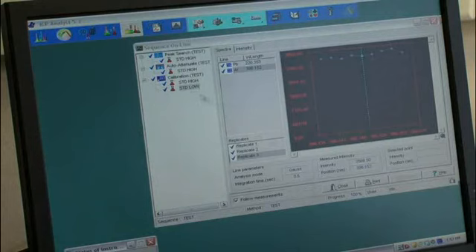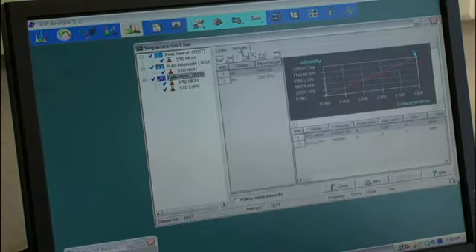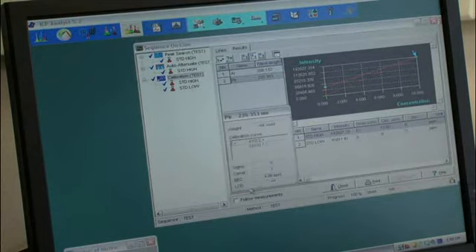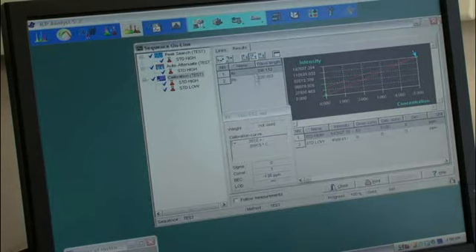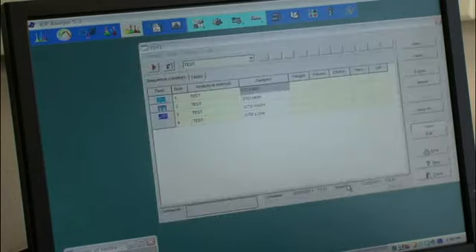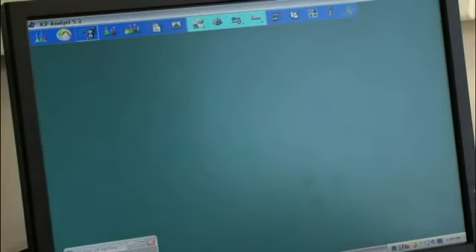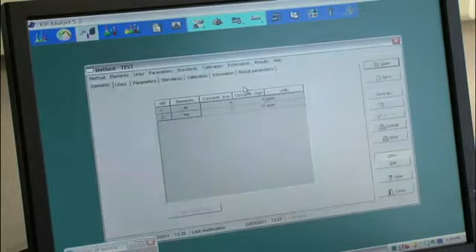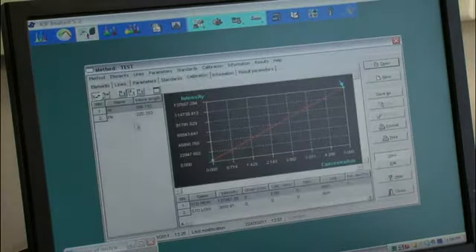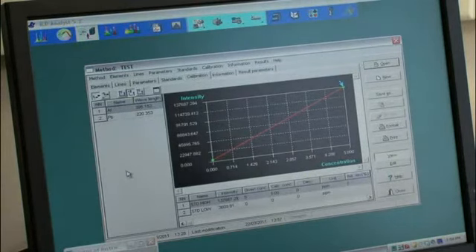Okay, so here we can click to see what our calibration curve looks like. And here it'll tell us the detection limit. Well, it'll tell us what the intercept is. And then what it'll also do is put that back into the method. If we go to the method and go in calibration, it'll put the curve in there too. So then whenever you do an analysis, it'll look at your curve and compare those intensities and tell you what the concentration is.